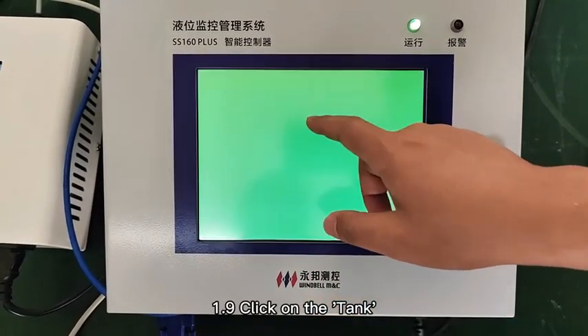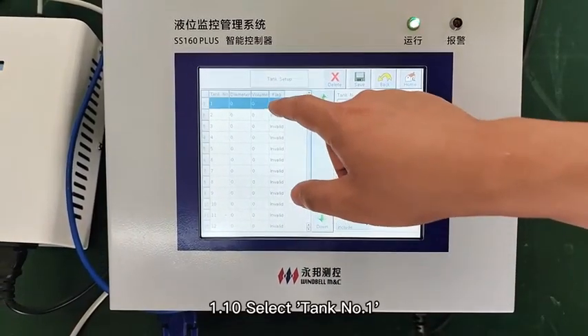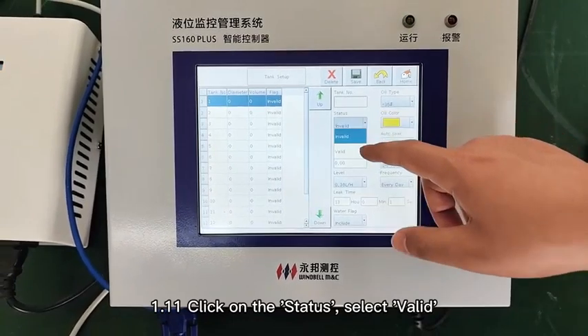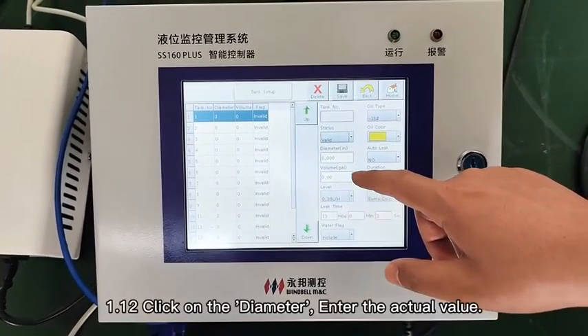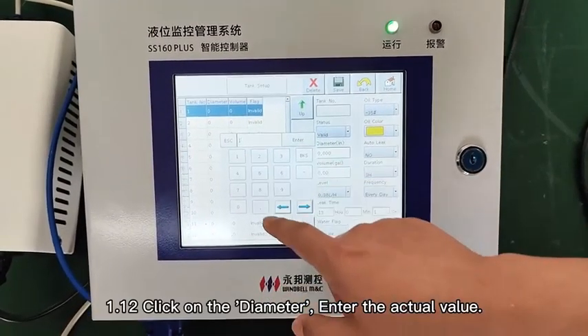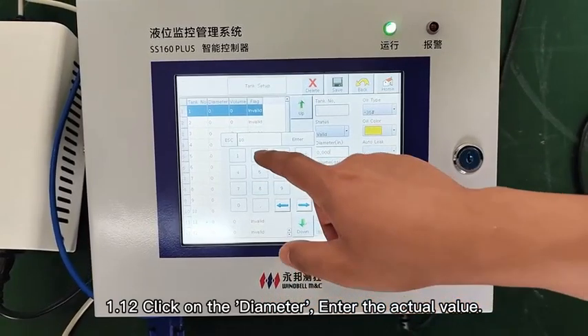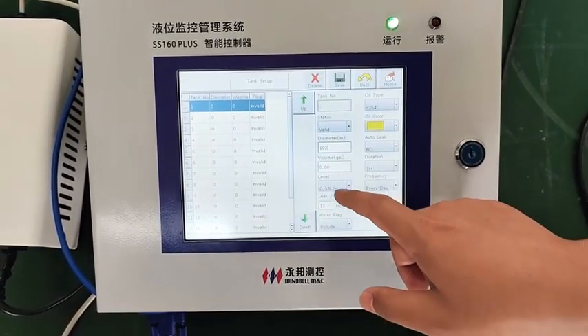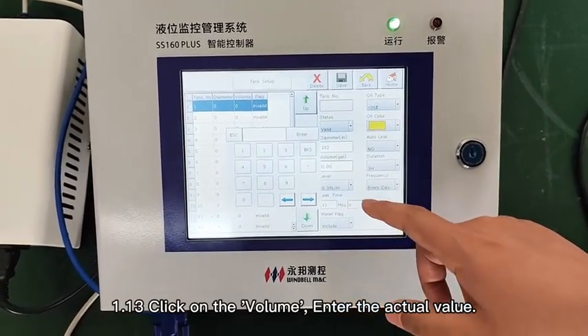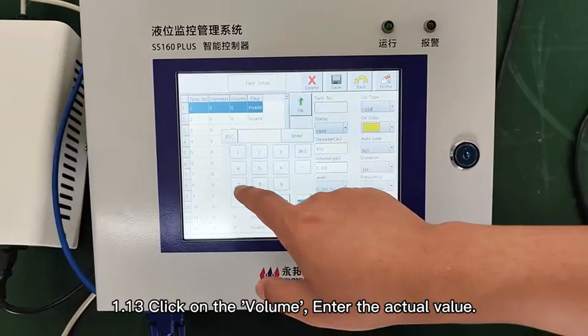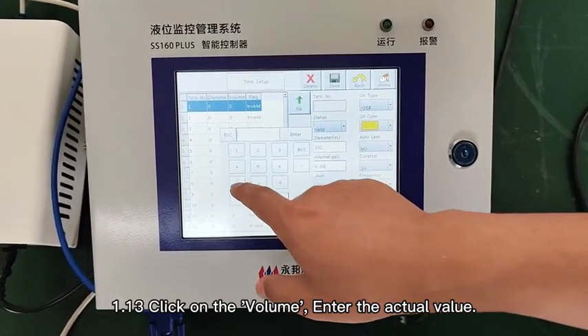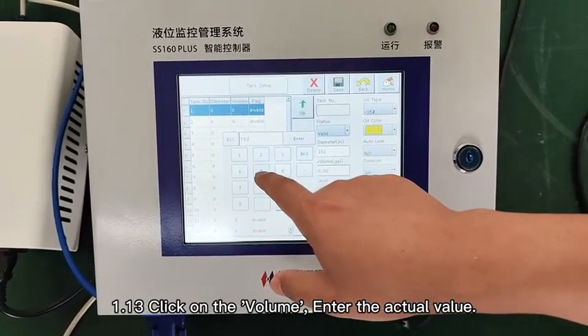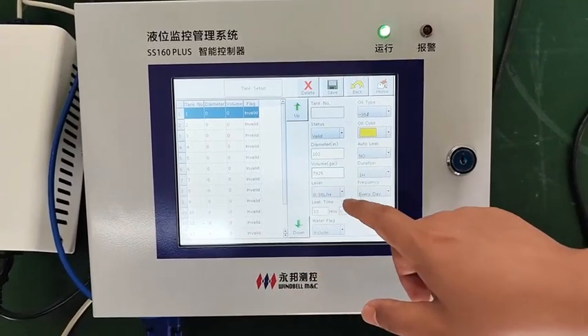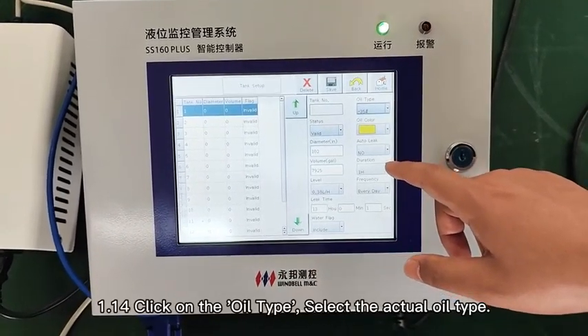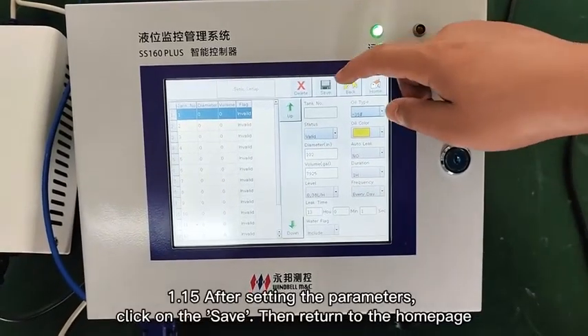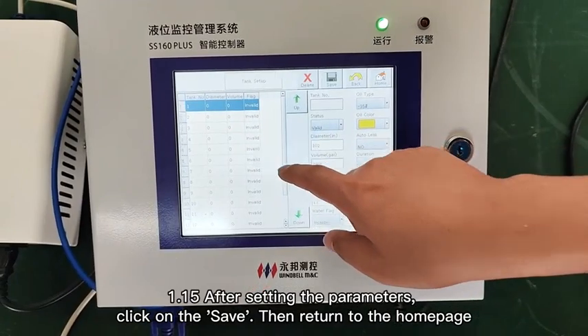9. Click on Tank. 10. Select tank number 1. 11. Click on Status, select Valid. 12. Click on Diameter, enter the actual value. 13. Click on Volume, enter the actual value. 14. Click on oil type, select the actual oil type. 15. After setting the parameters, click on Save, then return to the home page.